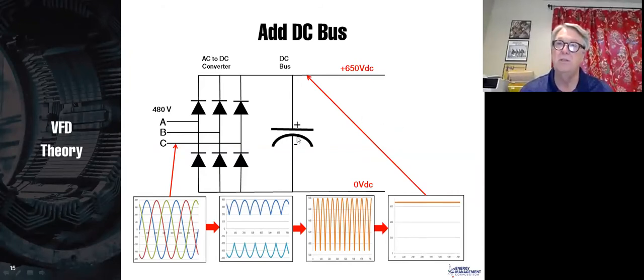So that DC bus charges to 650 volts, and with the reservoir there, it becomes very smooth. The purpose of the capacitor is to smooth that out. So the thing that's actually running our motor is not the AC system, it is the capacitor. All of the power coming from the drive to the motor comes from that capacitor, and then this AC to DC converter is responsible for keeping that capacitor charged.